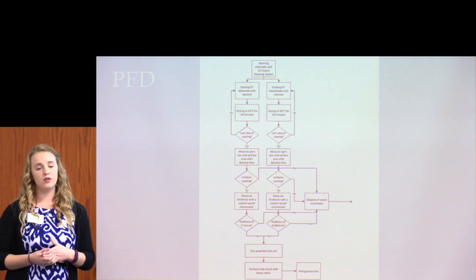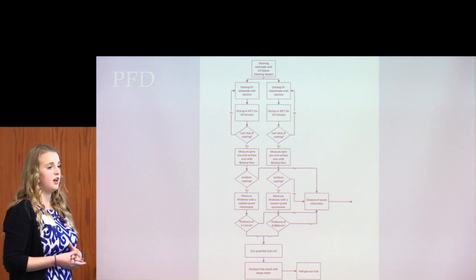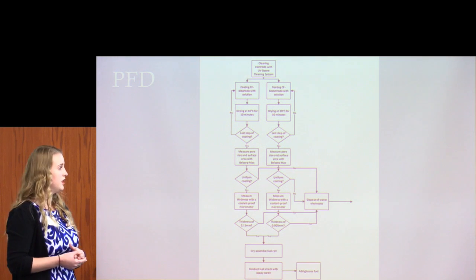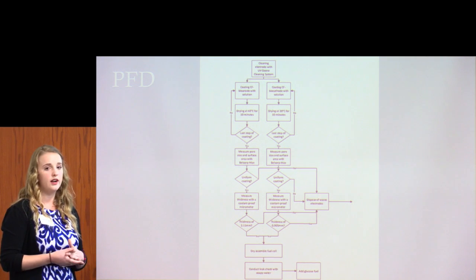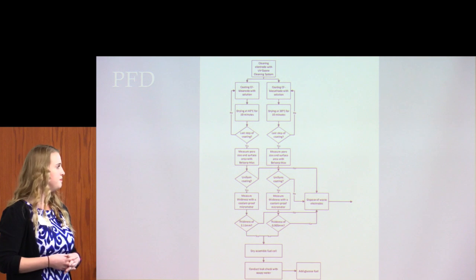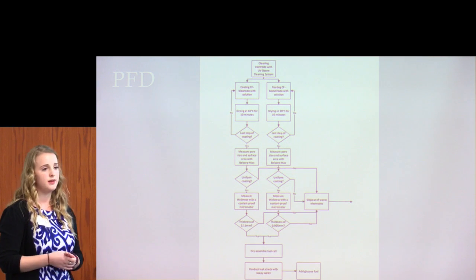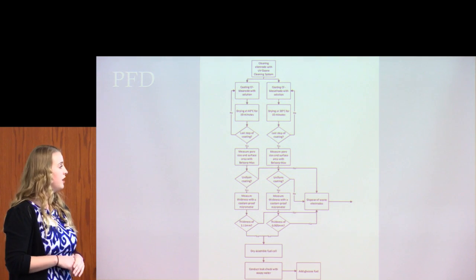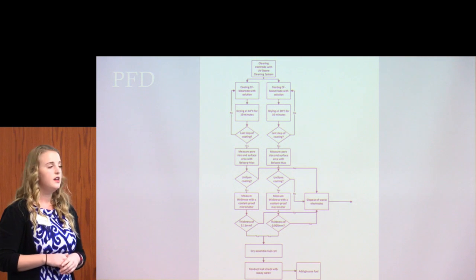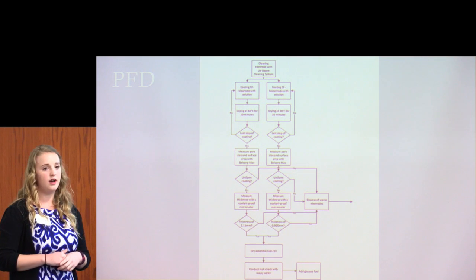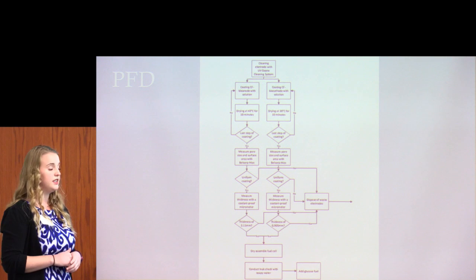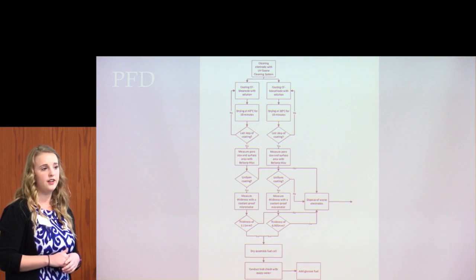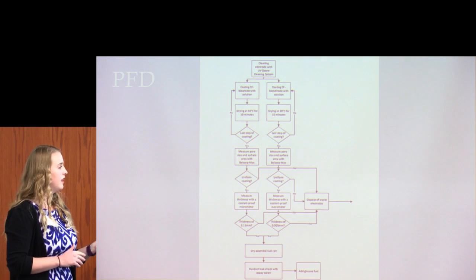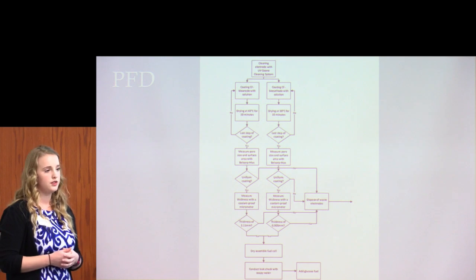However, I would like to note that this failure rate for the electrodes is very low because we have a great quality management system where we have great SOPs, so everything's standardized. So after we go through these measurements, we move back into the dry assembly of the fuel cell. And once this dry assembly is completed, we do a leak test with soapy water to verify that it was assembled correctly. And then lastly, we add the fuel, which is glucose, to the fuel cell.